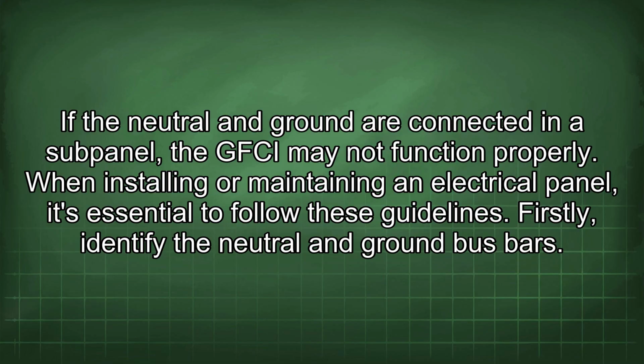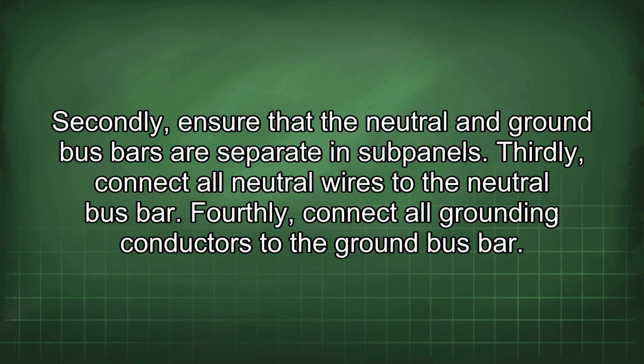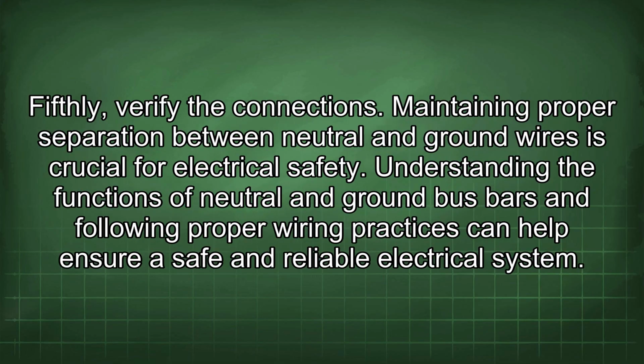Firstly, identify the neutral and ground bus bars. Secondly, ensure that the neutral and ground bus bars are separate in subpanels. Thirdly, connect all neutral wires to the neutral bus bar. Fourthly, connect all grounding conductors to the ground bus bar. Fifthly, verify the connections. Maintaining proper separation between neutral and ground wires is crucial for electrical safety.